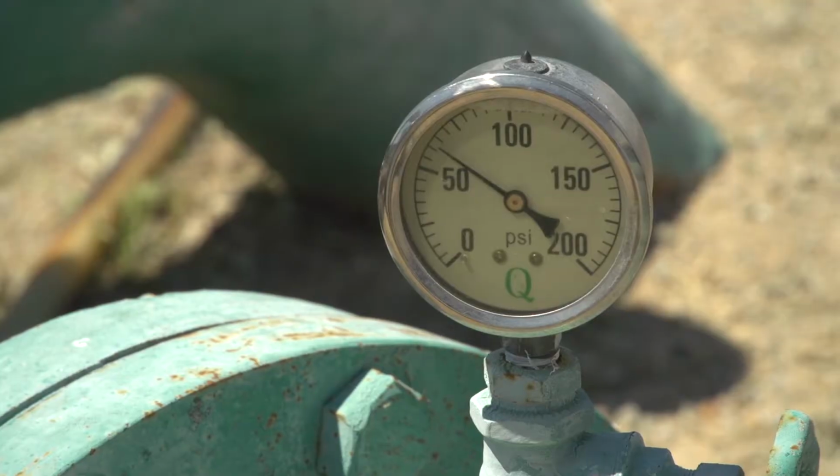So yeah, it's strange, but I need to see if that is a 100 psi pressure gauge. I think so. So what was the reading? 60. So there would probably be 1 or 2 or 3 psi difference between those two pressure gauges. What would you expect across that filter? Wouldn't you expect like 4 or 5 pounds? Yeah, that's what I expect, maybe between 5 and 10 when it needs washing. So it's probably a little bit off.